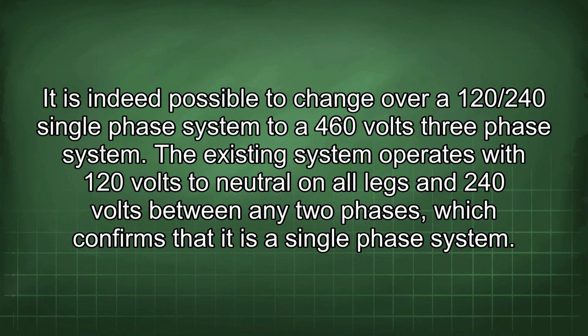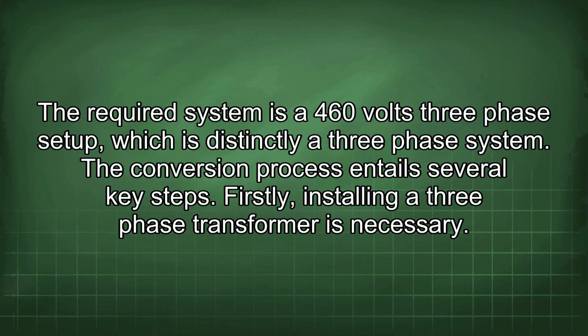It is indeed possible to change over a 120/240 single-phase system to a 460 volts three-phase system. The existing system operates with 120 volts to neutral on all legs and 240 volts between any two phases, which confirms that it is a single-phase system. The required system is a 460 volts three-phase setup, which is distinctly a three-phase system.